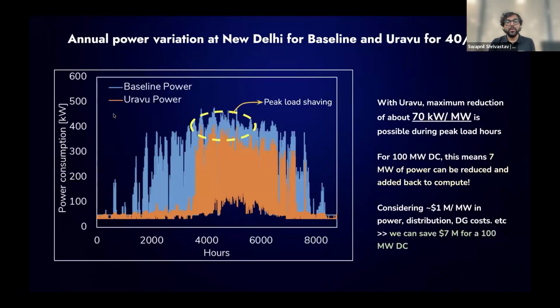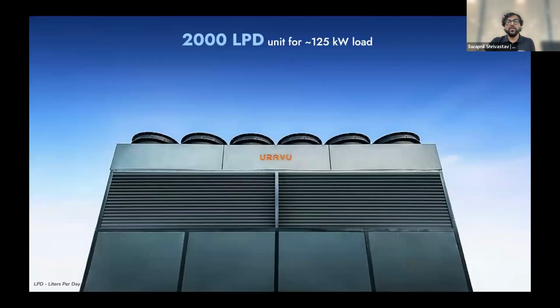We also use a lot of tools to analyze your overall peak load shaving. As Dr. Srinivas was also saying, a lot of this design today is for peak load. But as you can see here, the baseline power is hardly utilized for peak loads, hardly 20% of the time for a Delhi kind of place. For most of the time, it's less than 50, 60%. So you're designing extra for so many hours, which is not even needed. Whereas our solution shaves that peak load while also maintaining more flexible performance throughout the year. That leads to more savings in cost, reduction in DG sets, and reduction in your power and distribution requirements. And roughly for a 100 megawatt data center in Delhi, we can save $7 to $10 million just in initial capex with our solution.